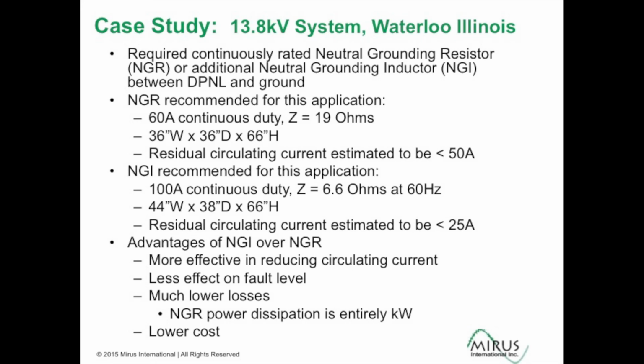An NGI, because we're dealing with inductance, which is 2 pi FL, so 2 times the frequencies, and if the frequency is 3 times the fundamental, we can put in less impedance in the inductor than the resistor, and it has less resistance as well, so there's less losses associated with that NGI. Slightly larger box configuration, but better performance in reducing the residual circulating currents. So either of these approaches would work, but when you can't or don't have access to the transformer's neutral connection, we need to look at adding either an NGR or NGI to the DPNL application.